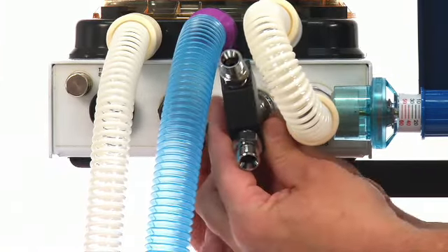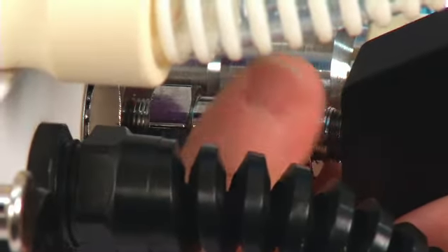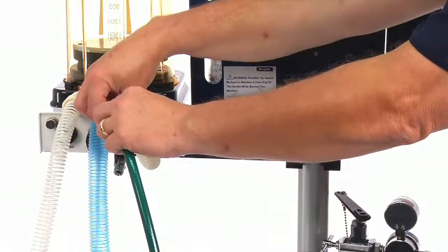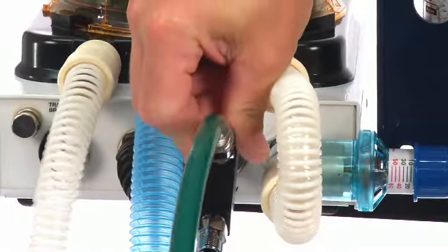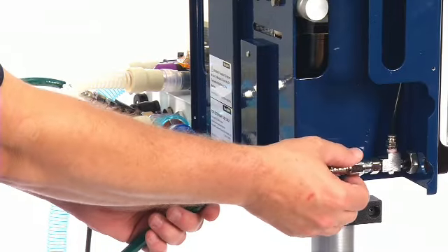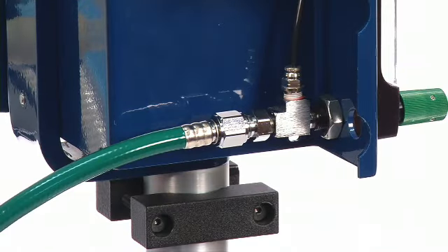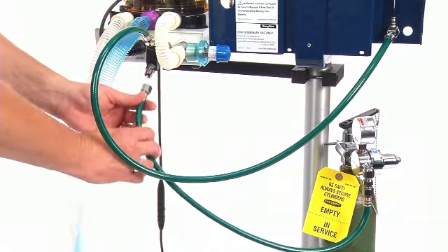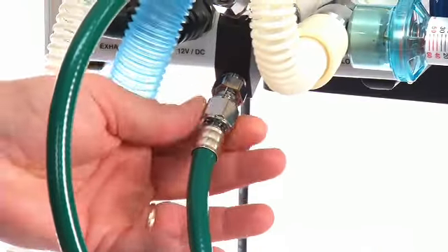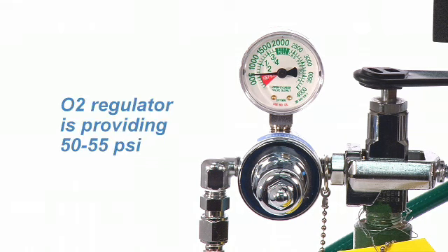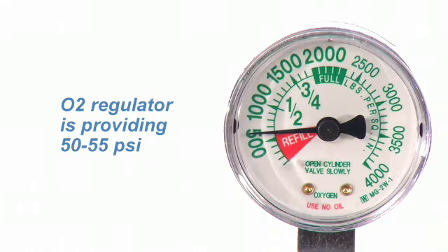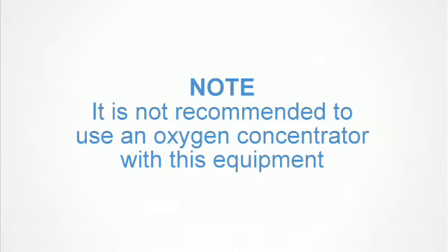Connect the DISS Y piece to the back of the ventilator at the oxygen inlet. Connect the 24-inch green oxygen hose to one leg of the Y piece and connect the other end to the DISS fitting on the anesthesia machine. Connect your main O2 supply hose to the other leg of the Y piece. Please ensure that the regulator connected to your main O2 source is providing 50 to 55 psi. It is not recommended to use an oxygen concentrator with this equipment.